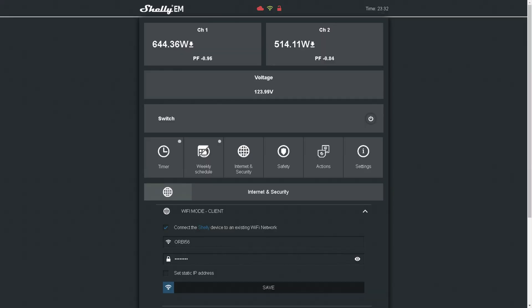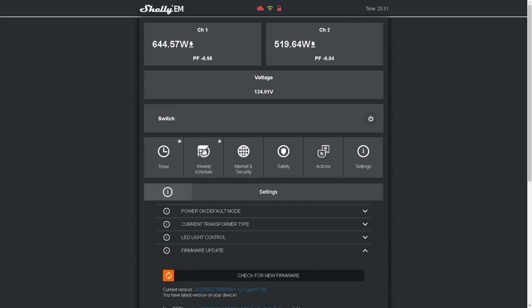I will definitely be doing another video with one of these to control a contactor later on. With the energy meter installed and powered on, I can access the ad hoc WiFi network from my phone and navigate my browser to 192.168.33.1, like all Shelly devices. Once there, I can set up the WiFi connection, then switch to my computer and log back into the device to check for firmware updates, set up MQTT or other settings, and set a device password. Then I'll go over to Home Assistant and add the device, which is automatically detected — all I need to do is give it my password and the area the device is located, though I won't bother setting that since this is the whole-house power meter anyway.